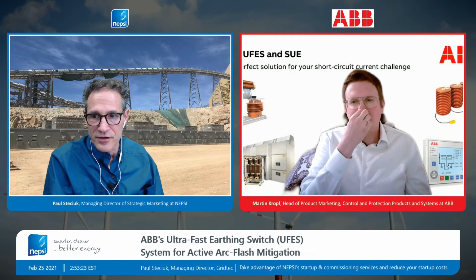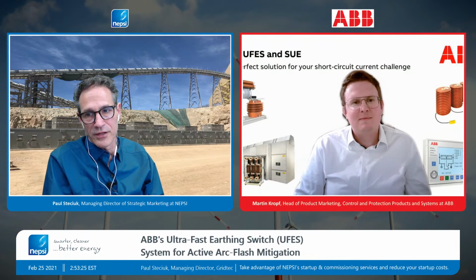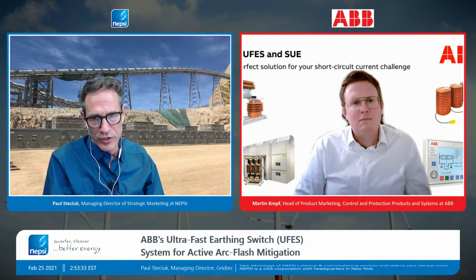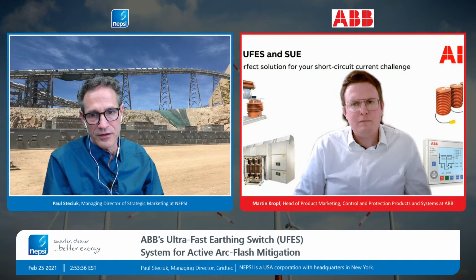Douglas asks: please clarify that ultimately the UFES is depending on an upstream OCPD to open, must be a power circuit breaker maybe. Is that clearing time not determined by the arc flash energy in the subject equipment?